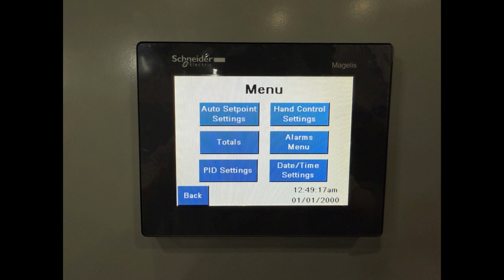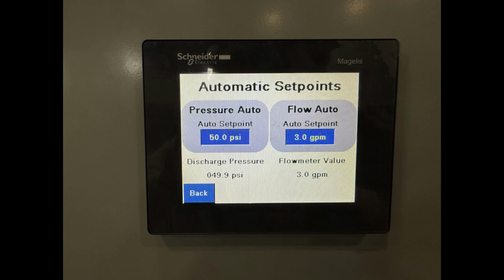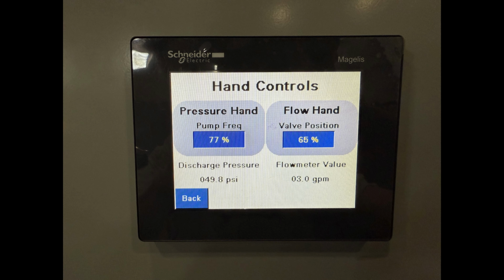If we move on to the menu, we can see our different pages that I'll go through individually here. For our automatic set points here, this is for auto mode. We are maintaining 50 psi for our PID and also 3 gallons a minute for our flow PID. If we went back to menu and continued on, we could see our hand controls. This is for hand mode. You can select the frequency you want and also the position that you want the valve open.